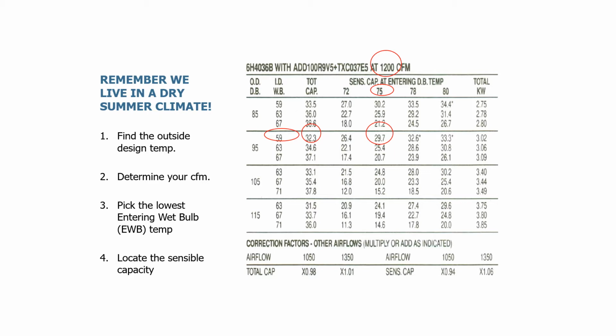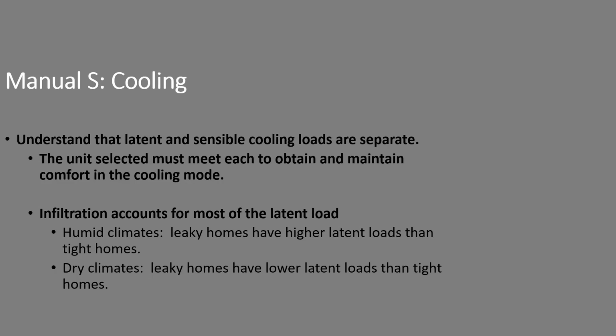59, that's a good one for us. And then locate the sensible capacity. Here we have the total capacity, and again, that's the sensible plus the latent. And here, our 3-ton machine is giving us 30K with the sensible capacity, which is really good. Please notice if we pick 67, the sensible capacity drops all the way down to 20, but the total capacity goes up to 37. I really urge you when sizing your air conditioners in the Northwest to pick the lowest indoor wet bulb you can. That's the best indication of the sensible capacity, that ability to lower the dry bulb temperature in the house.